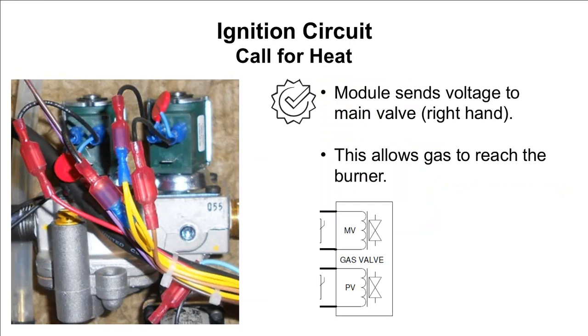If the module is satisfied that there is an air current and the blower pressure switch has closed, at this point, it sends voltage to the right-hand valve. Now, again, if you've got your manometer hooked up already, you will see that static pressure that we mentioned earlier drop down to dynamic pressure. This is a really good way to also test, are both sides of my circuit working? If DC and AC are happy, you'll see first static, and then you'll see dynamic. It's a really easy visual indication to check the unit's operation.